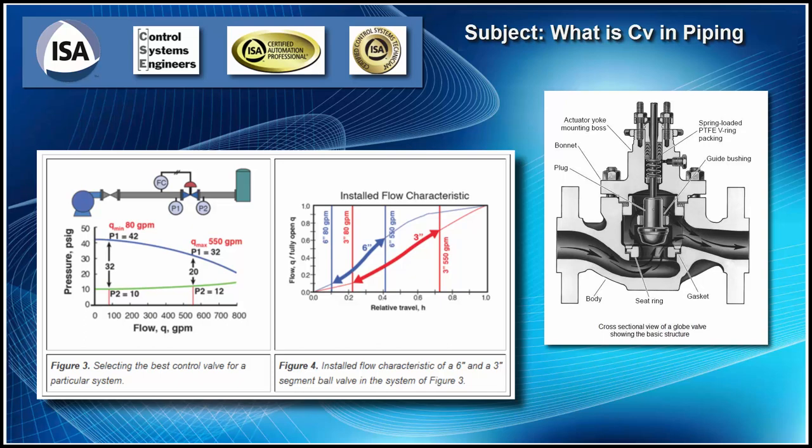And as you know, if we speed up our flow in our pipe very much at all, we have a tremendous head drop across that pipe. So that differential pressure will go away from the valve. And this is exactly what I'm talking about. You can actually get enough pressure drop that you can bottleneck and choke yourself up, and you just won't get the flow you're expecting through there. So be careful about this. I'll try to talk about this more when we size valves. Okay.